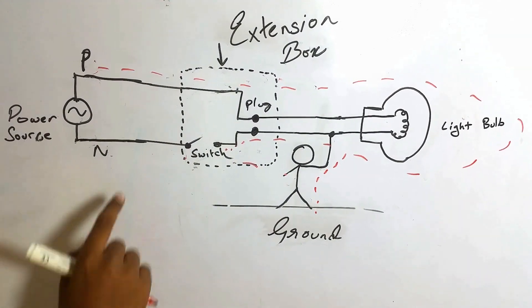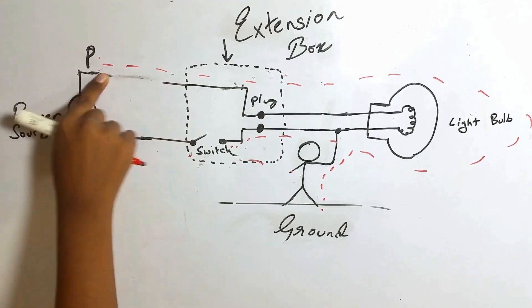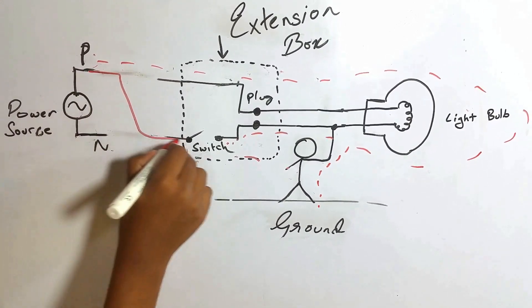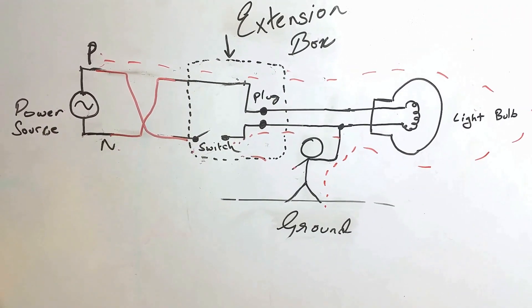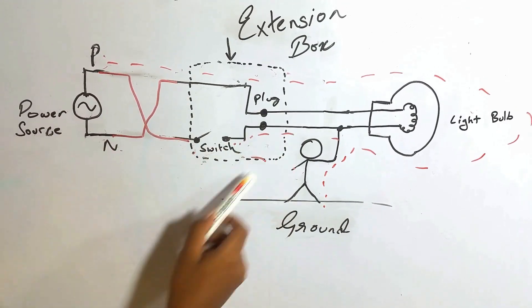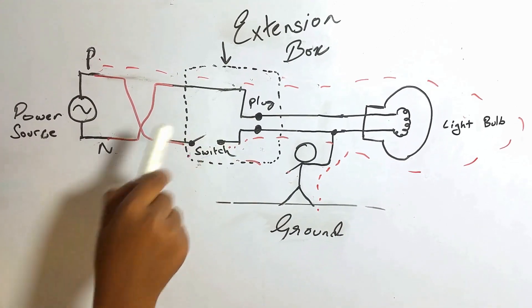The way to fix this is to connect the switch in the phase. So now what happens is the switch is turning off the phase, so there will be no current coming from the phase and no current flowing through the light bulb anymore. So you won't get shocked when you touch this light.